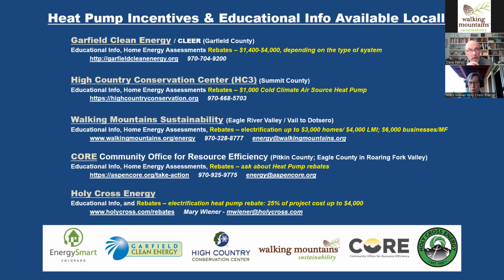I'll give an example where it could be tricky. If your house needs more than that 5-ton system, say 60,000 BTU, and your house is bigger and needs 75,000 BTU or so in one system, you're not going to get a heat pump that can do that much. What will happen is the heat pump might be able to do your capacity at 25%, and then you're going to be a lot more dependent on electric. So in those kinds of cases, I might go with a hybrid heat pump gas system.